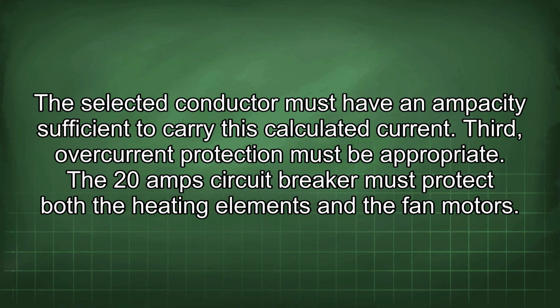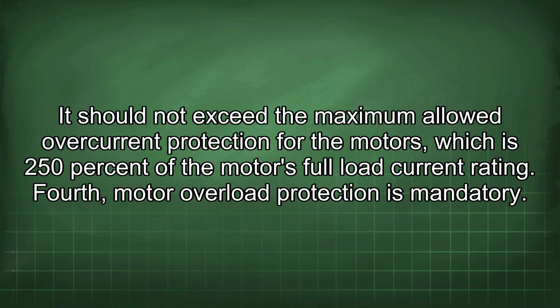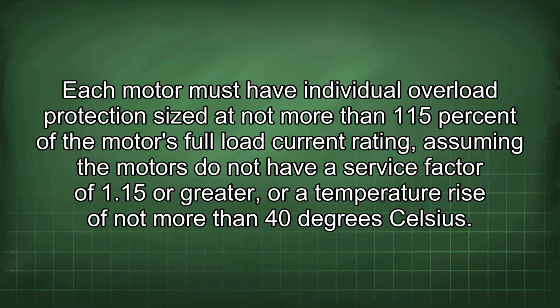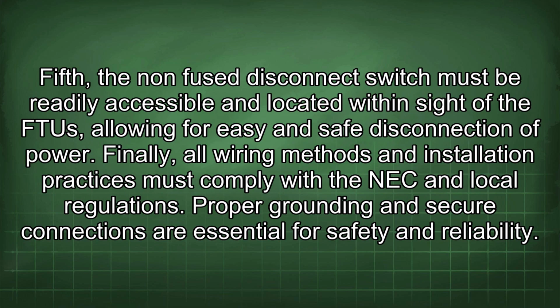Third, overcurrent protection must be appropriate. The 20 amp circuit breaker must protect both the heating elements and the fan motors. It should not exceed the maximum allowed overcurrent protection for the motors, which is 250% of the motor's full load current rating. Fourth, motor overload protection is mandatory. Each motor must have individual overload protection sized at not more than 115% of the motor's full load current rating, assuming the motors do not have a service factor of 1.15 or greater, or a temperature rise of not more than 40 degrees Celsius.